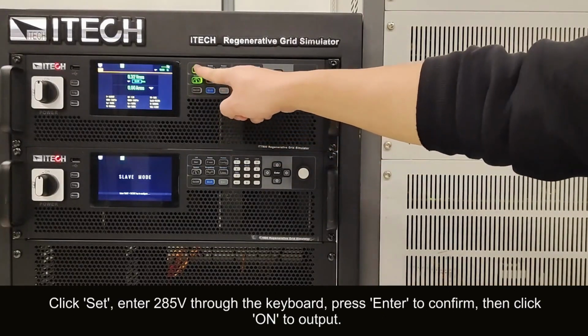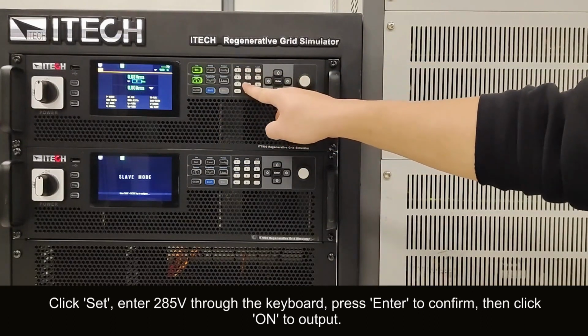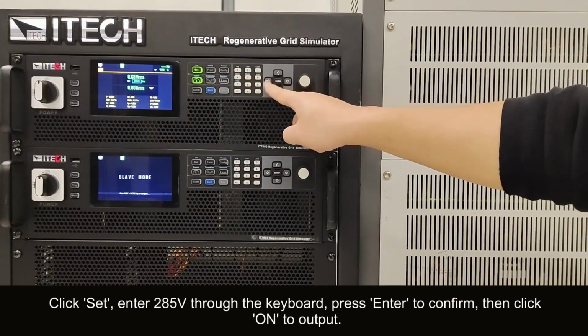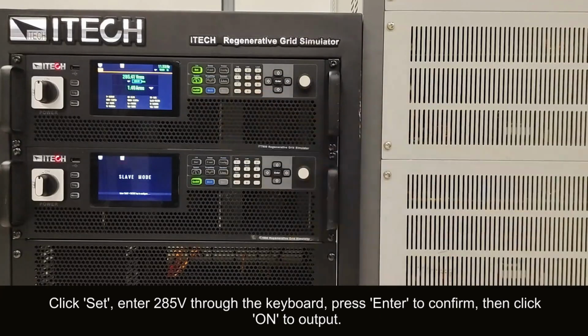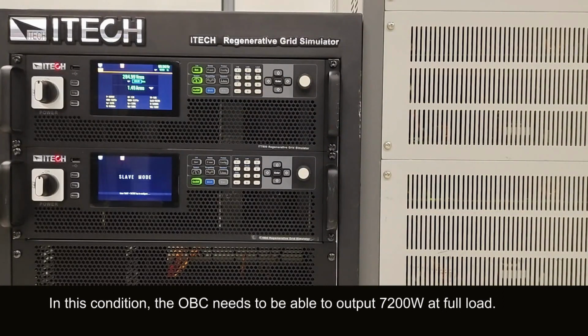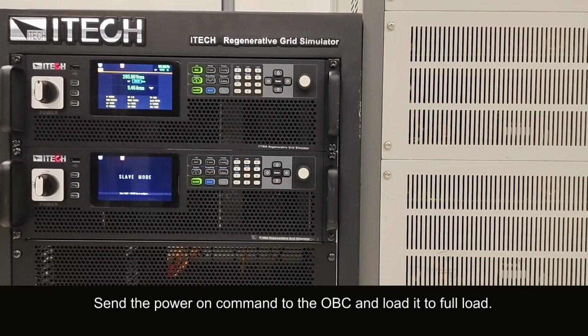Click Set, enter 285V through the keyboard, press Enter to confirm, then click on Output. In this condition, the OBC needs to be able to output 7200W at full load. Send the power on command to the OBC, and load it to full load.